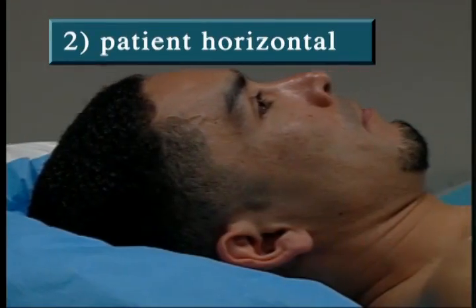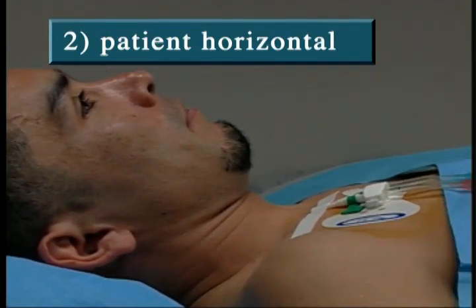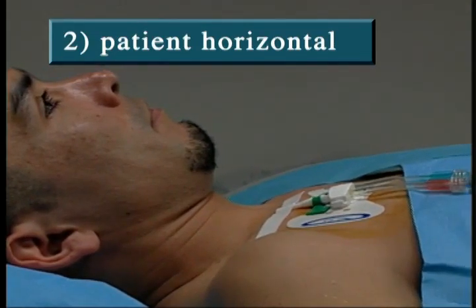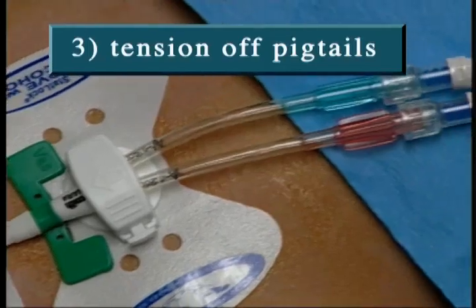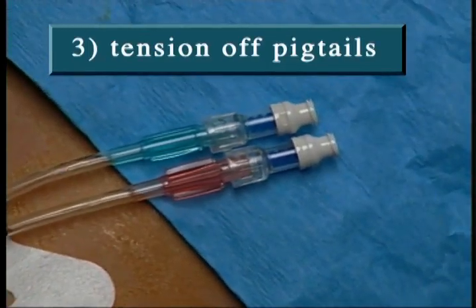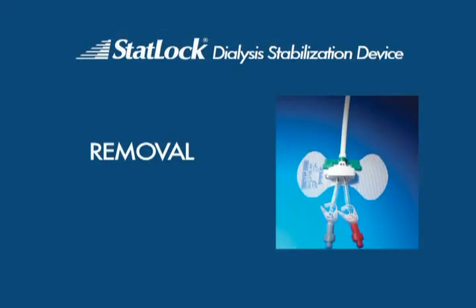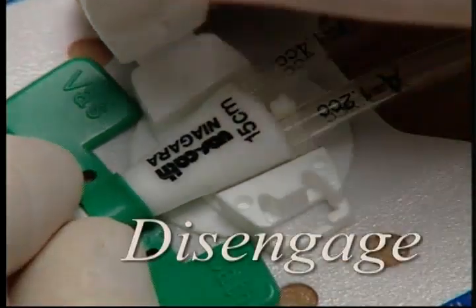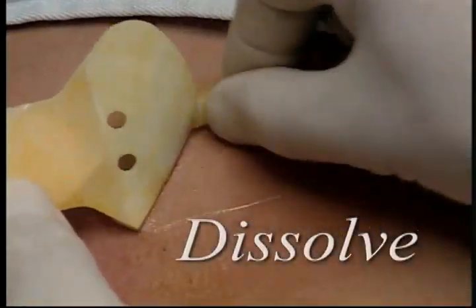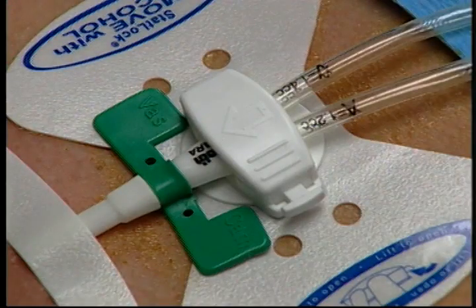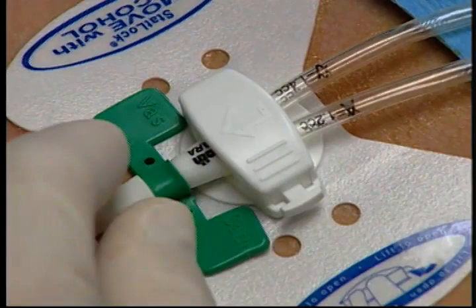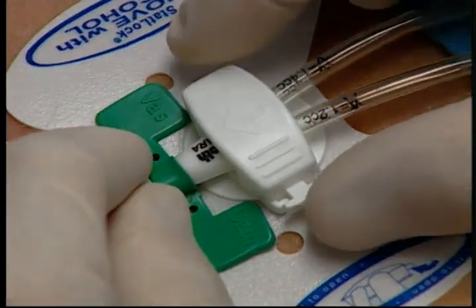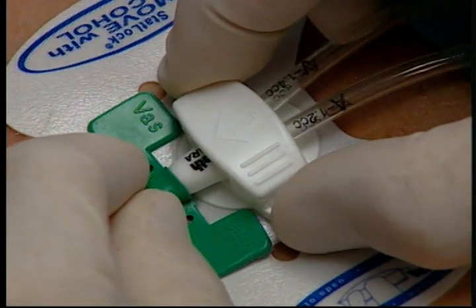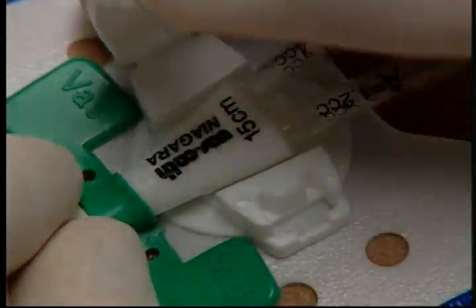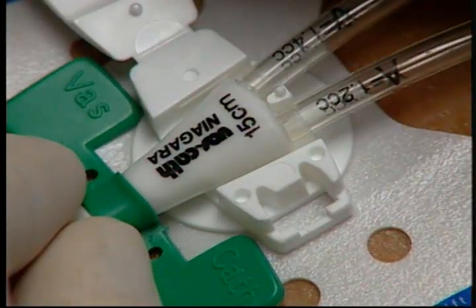Second, if at all possible, place the patient in a horizontal or near horizontal position. And third, take the weight off the catheter pigtails. Removing the StatLock Dialysis Stabilization Device is easy. Just disengage and dissolve. To disengage the catheter from the StatLock device retainer, first stabilize the catheter. Then place your thumb on the retainer tab. Press and lift the lid and gently lift or remove the catheter.